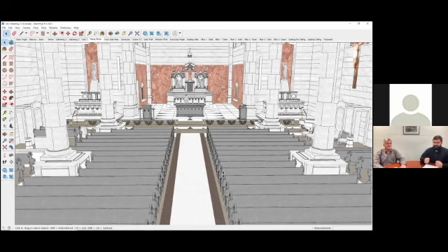Excuse me, Father, I was just going to add that with fan coil units, they do tend to be noisier than a chilled beam will be, which is what we're proposing. It's not as comfortable, the air tends to be more drafty, and the closer you are the more you feel and hear it. It's less controlled, and you don't get as much even coverage from those units. So that's one of the many reasons we're proposing chilled beams.